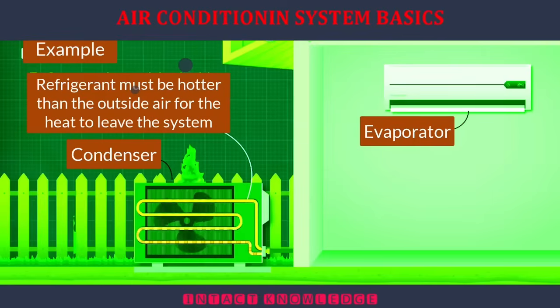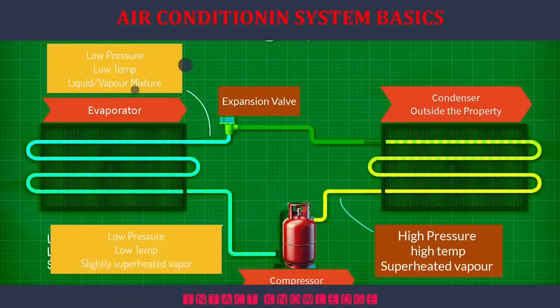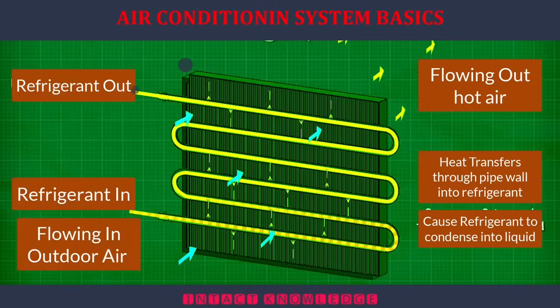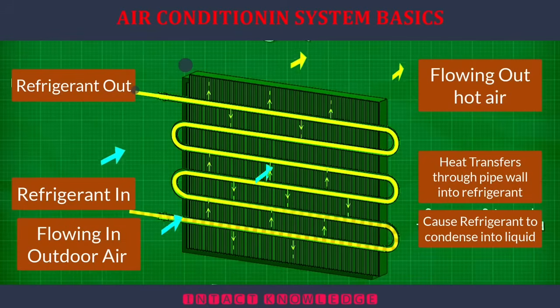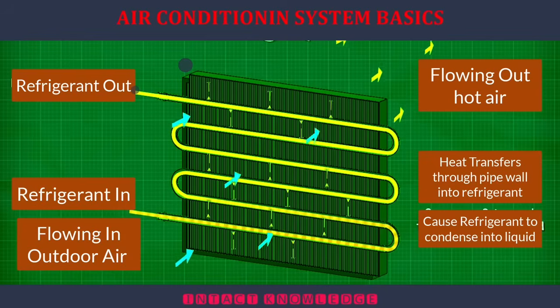The condenser is located outside, and the outside air might be very warm on a summer's day. As heat always flows from hot to cold, we need to ensure that the refrigerant is hotter than the outside air. Otherwise, the unwanted heat will not be able to leave the refrigerant and leave our system. A fan will help to blow ambient air over the condenser to remove this heat. So the outside air is entering warm, picking up heat, and leaving hot. As the heat is removed by the air, this causes the refrigerant to condense back into a liquid.